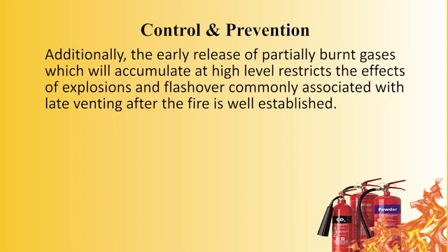What is that? The early release of partially burned gases, which will accumulate at high level, restricts the effect of explosion and flashover commonly associated with late venting after the fire is well established.